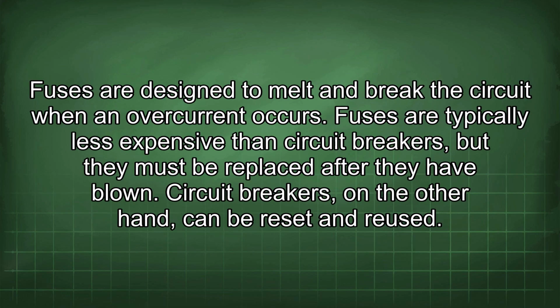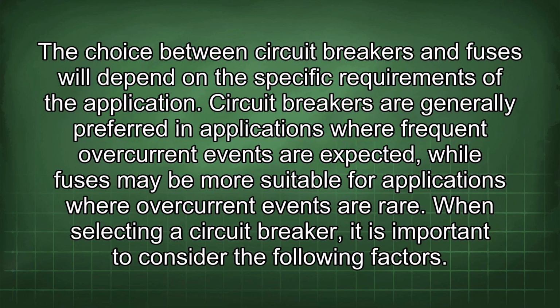Fuses are designed to melt and break the circuit when an overcurrent occurs. Fuses are typically less expensive than circuit breakers, but they must be replaced after they have blown. Circuit breakers, on the other hand, can be reset and reused. The choice between circuit breakers and fuses will depend on the specific requirements of the application.